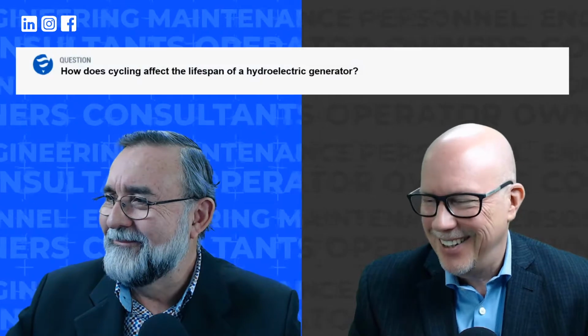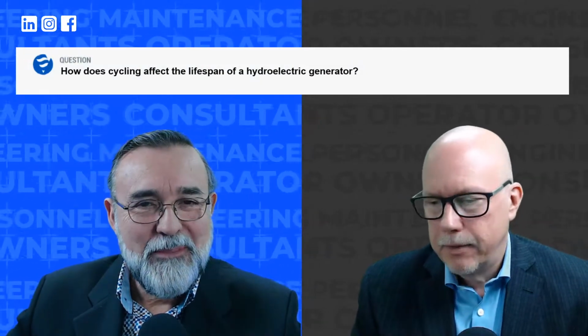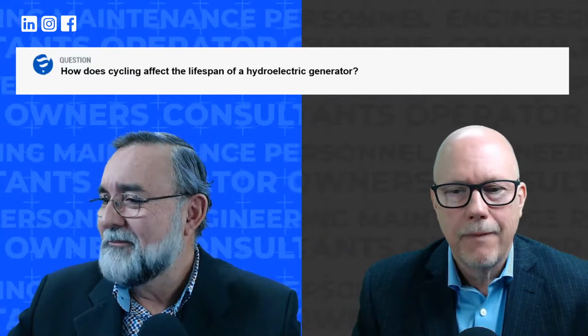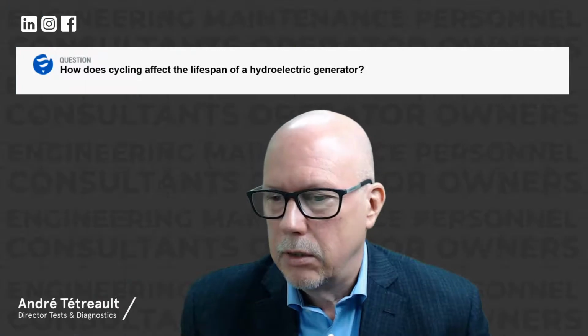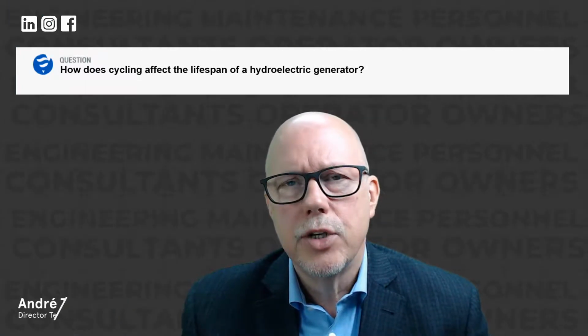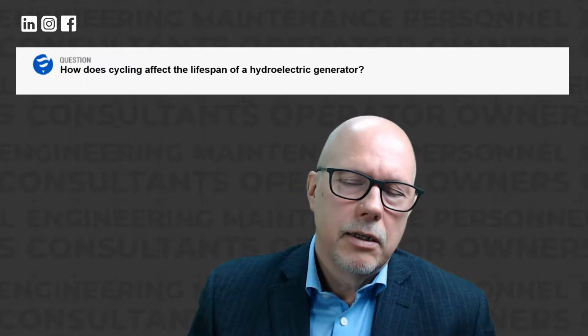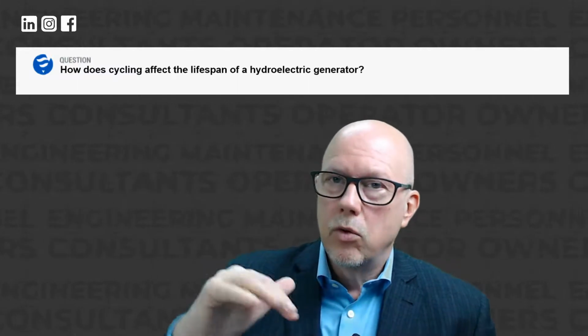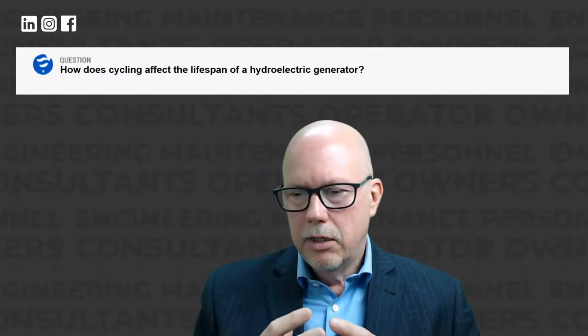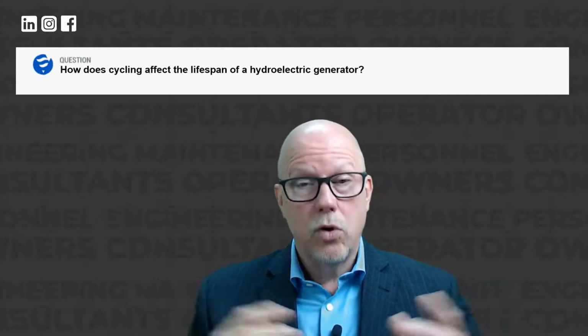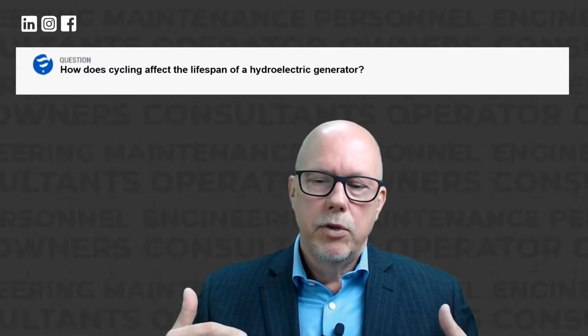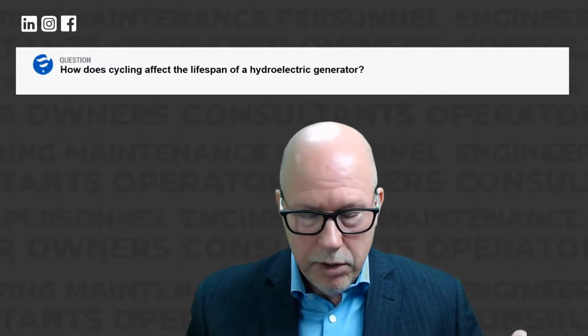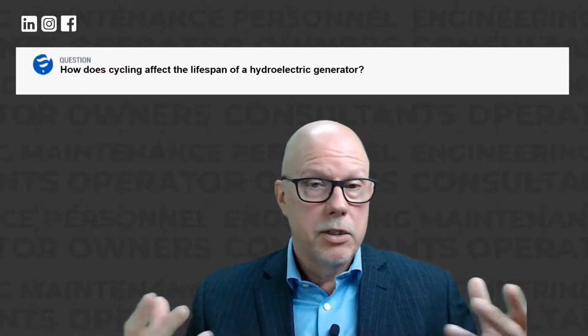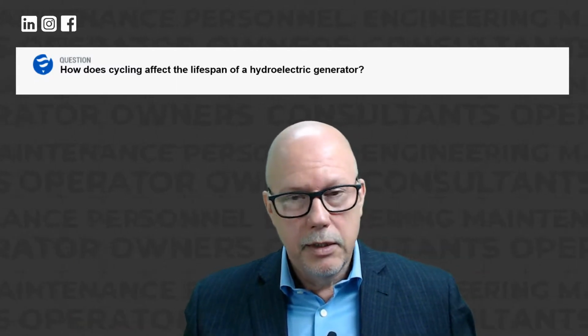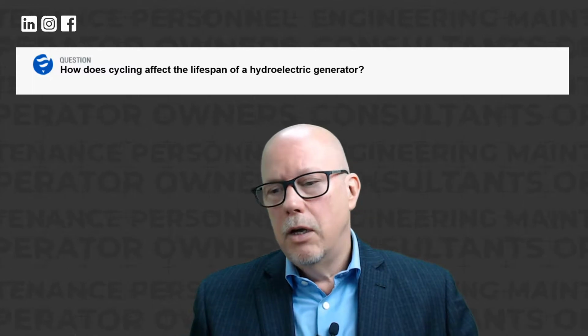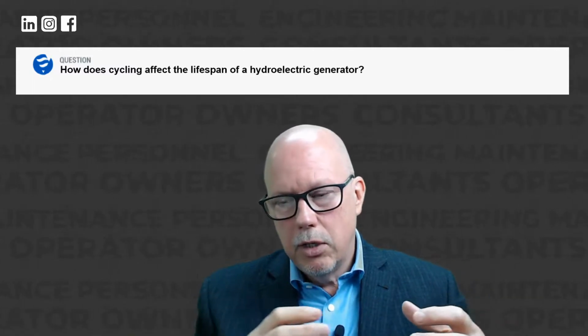Depends who you talk to. It's a well-known fact that a lot of the damage cycling does to generators—not just hydro generators, but generators in general—is the cycling, whether it's starts and stops or load cycling. It causes contraction and expansion of stator bars, stator core, stator frame, and all these components. So if you change the load, or start the unit from cold to hot, the heat generated by the copper, dissipated by the insulation and then the core, creates this expansion and contraction of the windings.